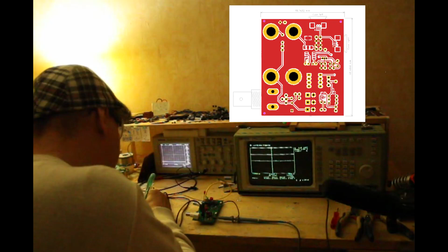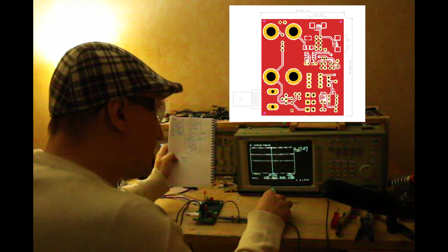But the interesting point is after a couple minutes we start to see an oscillation and the reading drops quite a lot. It is already dropping right now. So this meter is working well only when it is cold. When it is warming up, it will become far out of tolerance. We are about 1 minute after boot, and we see that we have 9.98 reading.